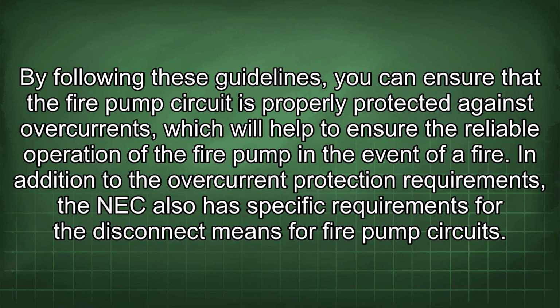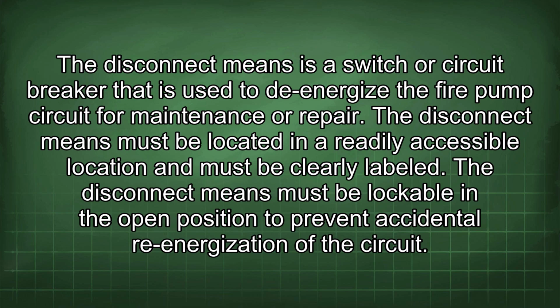By following these guidelines, you can ensure that the fire pump circuit is properly protected against overcurrents, which will help to ensure the reliable operation of the fire pump in the event of a fire. In addition to the overcurrent protection requirements, the NEC also has specific requirements for the disconnect means for fire pump circuits. The disconnect means is a switch or circuit breaker that is used to de-energize the fire pump circuit for maintenance or repair. The disconnect means must be located in a readily accessible location and must be clearly labeled.